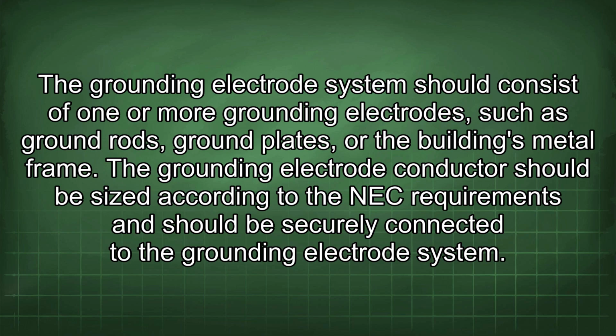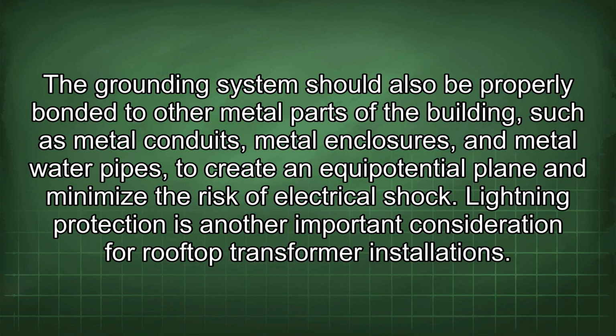The grounding electrode conductor should be sized according to the NEC requirements and should be securely connected to the grounding electrode system. The grounding system should also be properly bonded to other metal parts of the building, such as metal conduits, metal enclosures, and metal water pipes, to create an equipotential plane and minimize the risk of electrical shock.